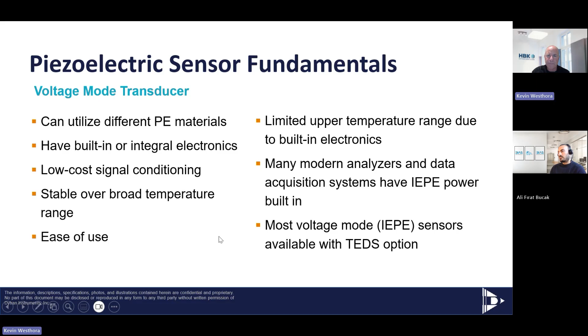As I mentioned earlier, almost every data acquisition system comes with an IEPE power option or ICP. And we can utilize TEDS in an IEPE accelerometer. I won't spend a lot of time on TEDS, but TEDS stands for Transducer Electronic Data Sheet. It means that I put the calibration certificate of the accelerometer inside the sensor so that when you plug it into your Siemens LMS system, it automatically calibrates. That's what TEDS means. And we can put TEDS in any voltage mode accelerometer.